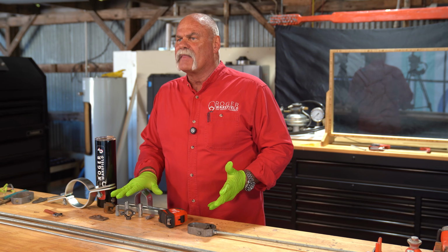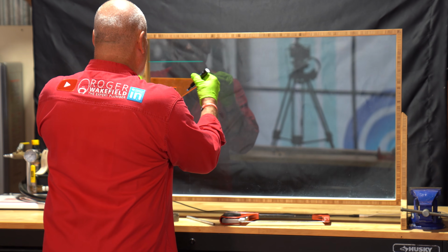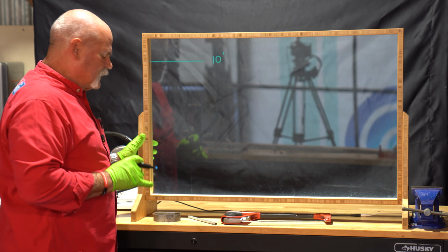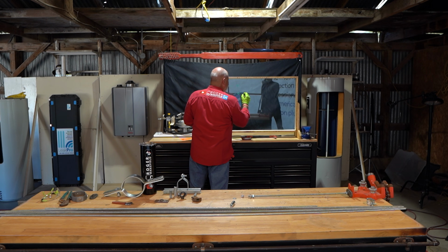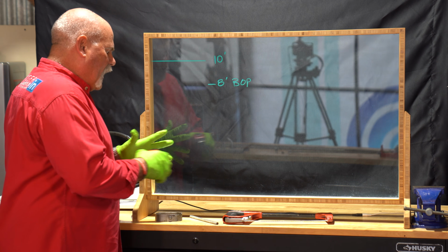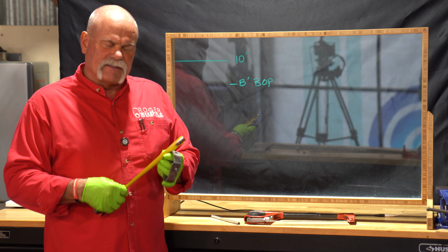And then we'll talk about some of these other ones and things that you can do to figure out what to do there. So say we've got a ceiling right here and we're gonna, again, use the 10 feet to make it easy to do the math right now. But you've got a 10-foot ceiling. And let's say, again, we're looking for an 8-foot bottom of pipe. Well, if I'm doing this on paper, trying to get ready to do a job, I don't have everything here with me, but I can get online and look and get the dimensions of my clevis hanger.